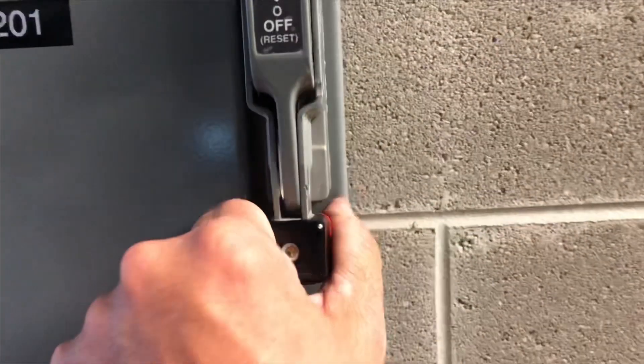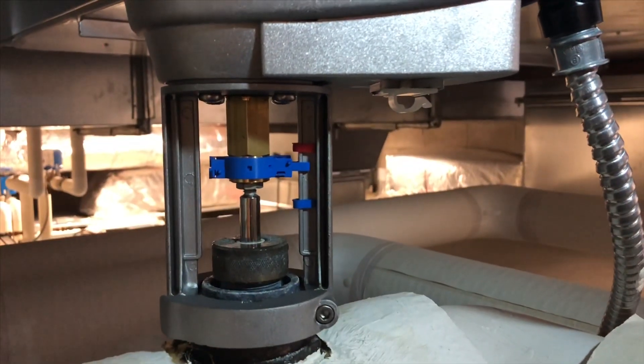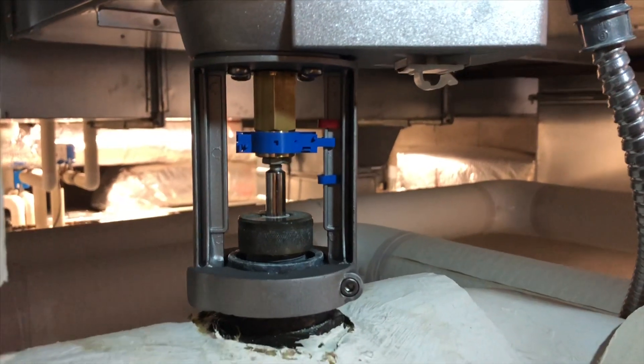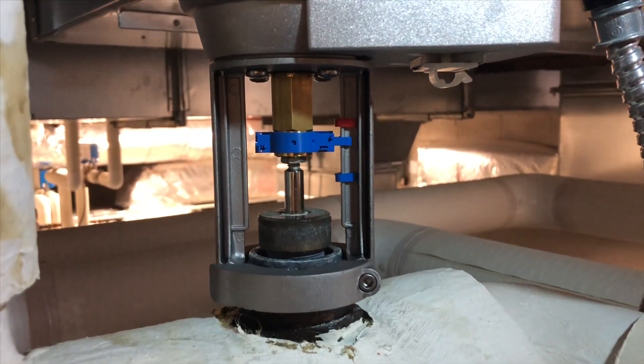I'm going to turn the power back on to our air handler. And put it on auto. And then we will turn on our controller. And our controller's on. And we'll see if we have any movement on our valve. Our cooling valve has done its calibration. It is holding its position and functioning properly.